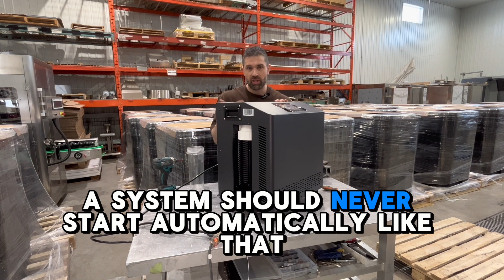I can't believe this, I'm just going to take it off. Right from the start, the pump shouldn't be running, it should wait. I need to be able to adjust the settings on the screen before the pump even starts turning, because maybe I don't want it running yet. Right now I have no hoses connected, there's no water in it, and the pump is already trying to run. What that's going to do is burn out the pump very quickly.